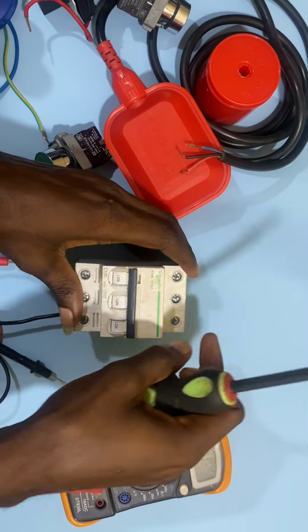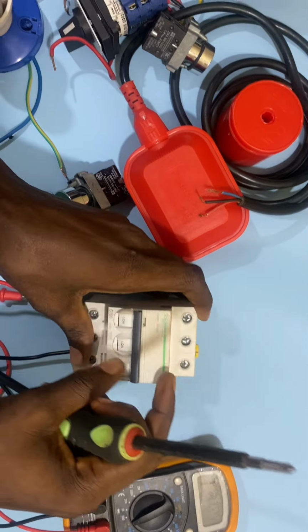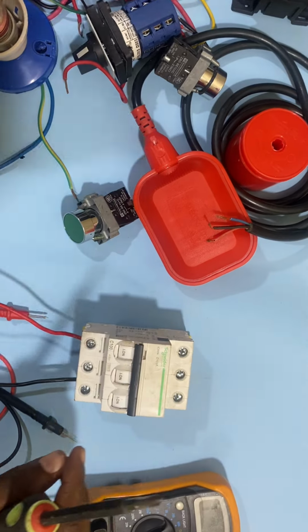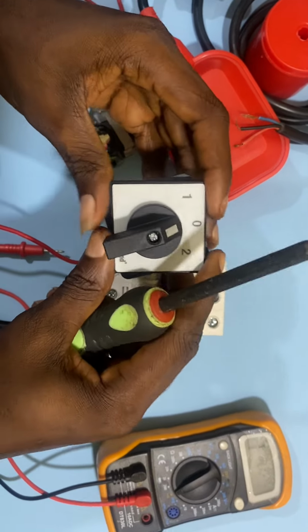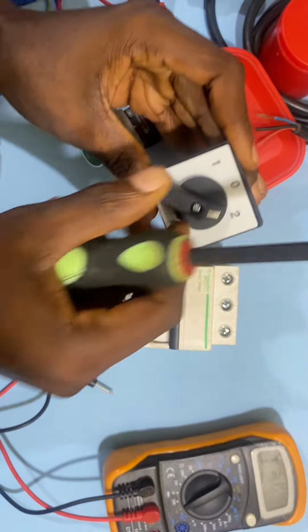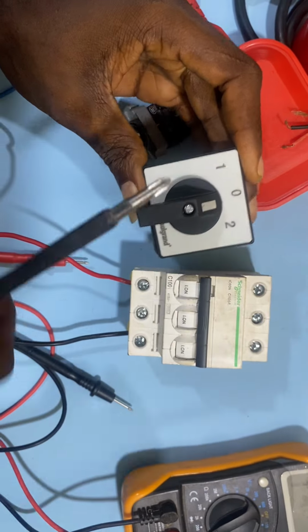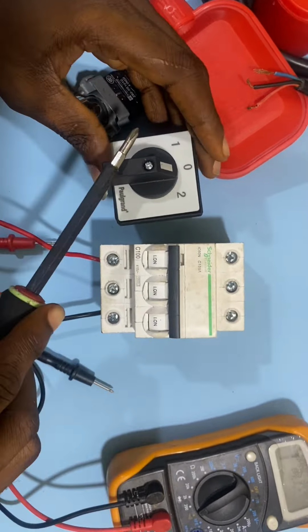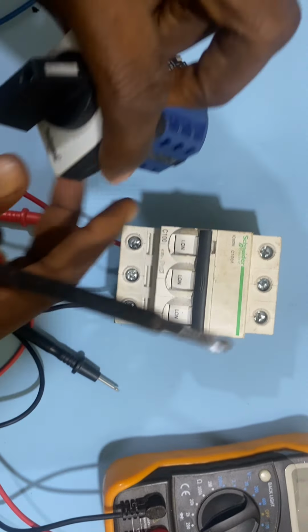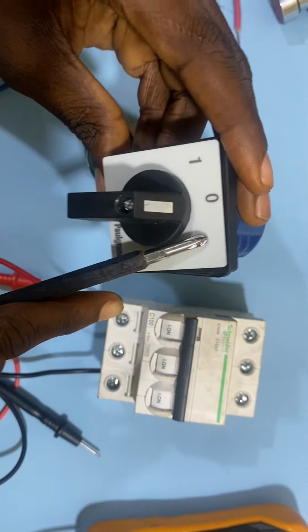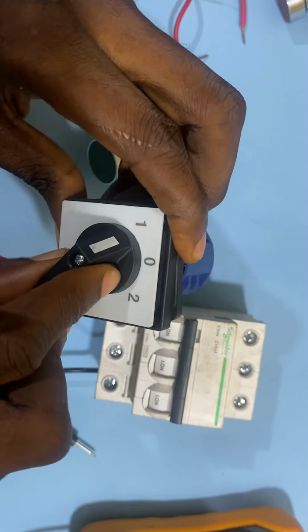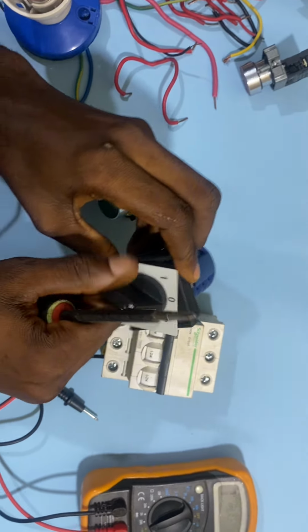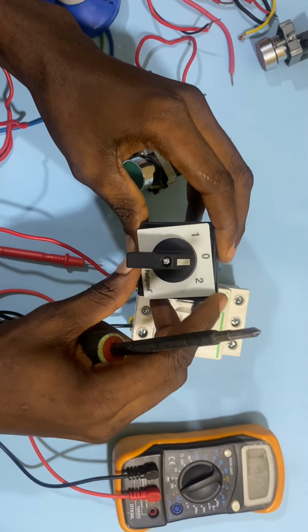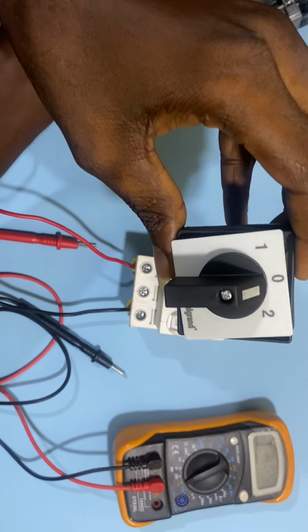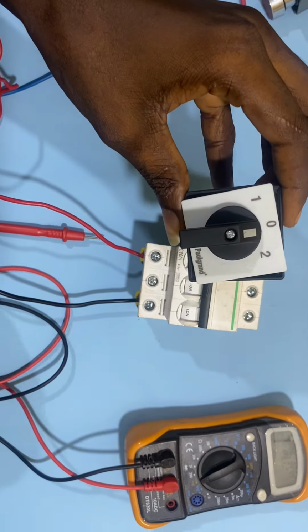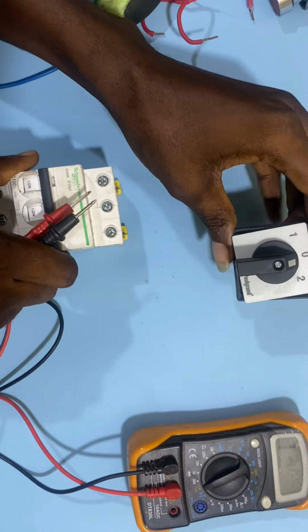The next thing is to take the output from the circuit breaker to our selective switch gear so that we can manually and automatically control the output load. So let me take it from the circuit breaker down to the selective switch gear. Before connecting, we need to check the operation of the selective switch gear, which side is the on position and which side is the off position. To do that, we use a multimeter. So I'm going to use my ohmmeter to carry out the experiment.